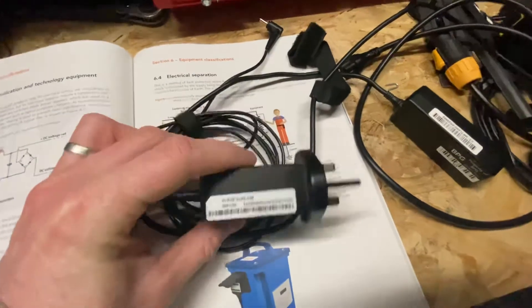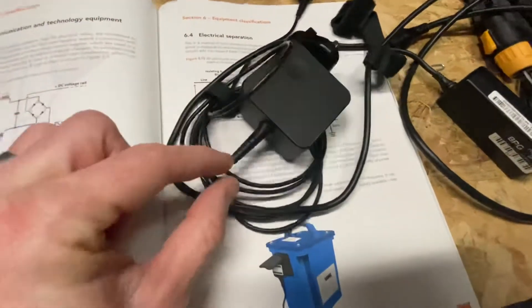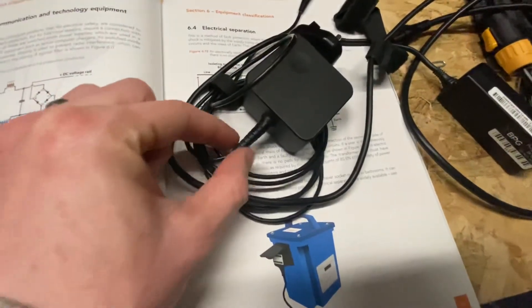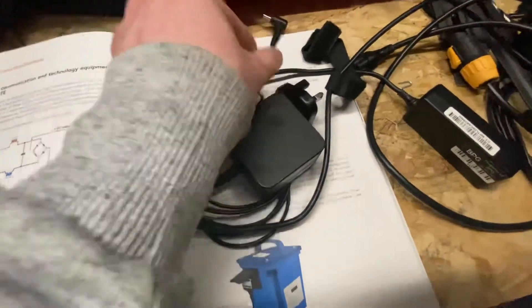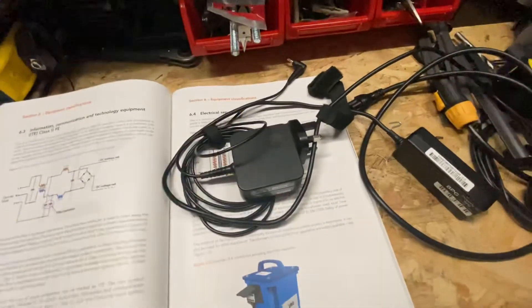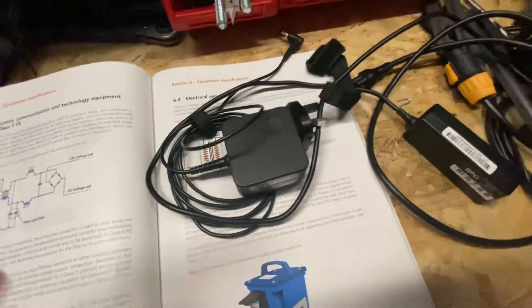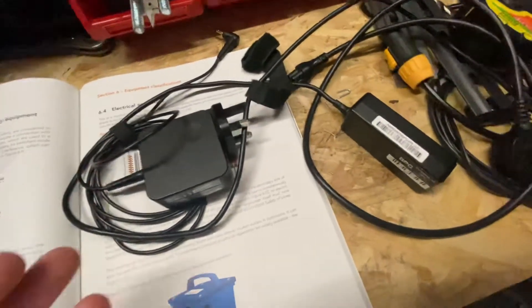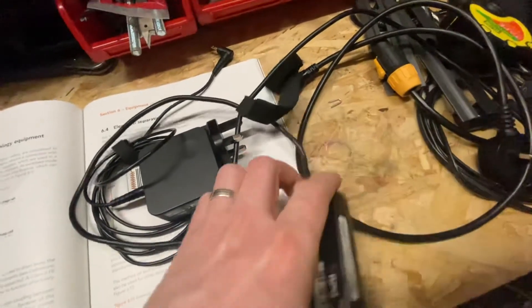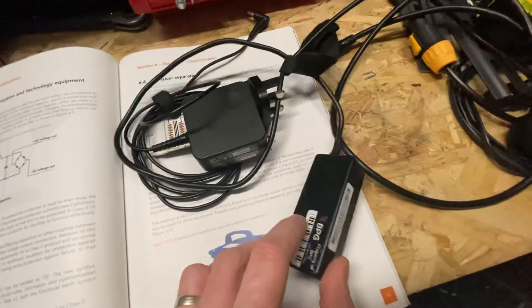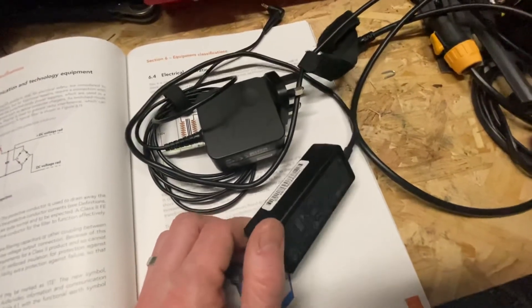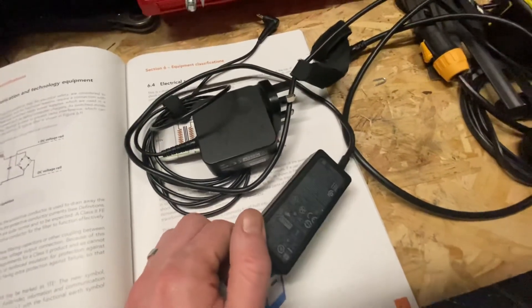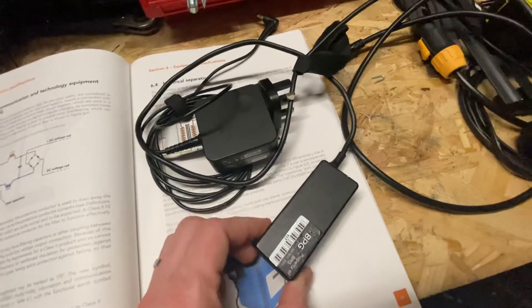You check for any signs of heat damage. You would check any damage to the cable here or this collar here, check there's no damage to the pin there. And again, I would just log it as a visual check. The frequency of the check would be for you to advise the duty holder or for the duty holder to decide how often they would want them done.